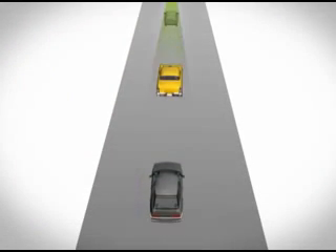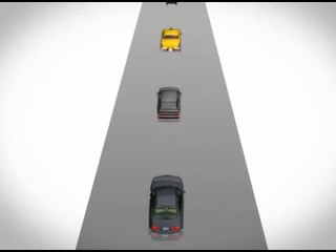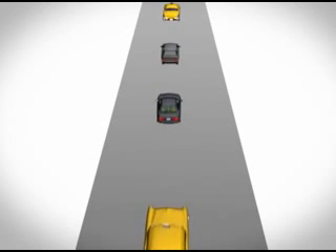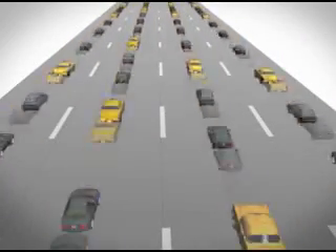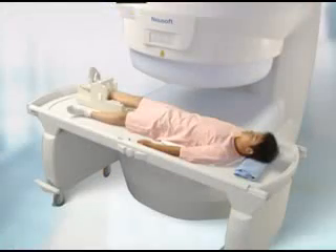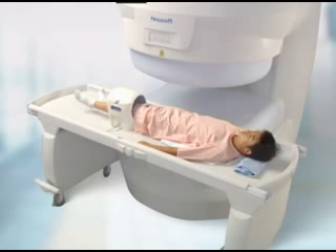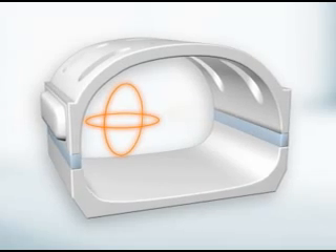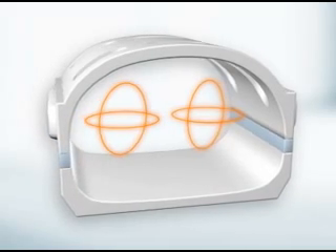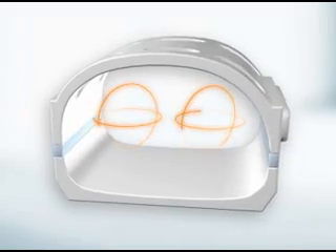The working principle of the four-channel platform is like an expressway — more channels, more vehicle flux. This platform greatly enhances the transmitting capacity with the Philips spectrometer and transmitting-receiving coils. The phased array coils realize the full potential of the multi-channel receiving mode, achieving the greatest capability because the four-channel spectrometer can work simultaneously, realizing higher sensitivity and bigger-scale imaging of the visual field.